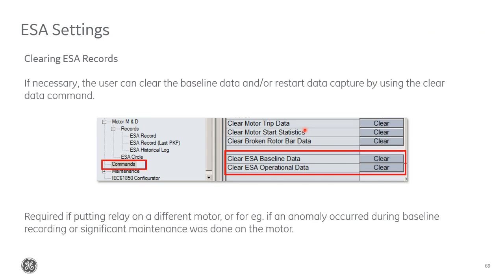Now, if you were to do any sort of testing on the ESA function, so you had some baseline values recorded that might not necessarily be applicable anymore, or if you took this relay out and put it on a different motor, that motor would have different characteristics, obviously. So in that case, if you still want to use ESA, you can clear all the ESA data that's been stored. You can clear all the baseline recordings and the actual operational data. You can wipe out everything and then start from scratch again. So this option is available.